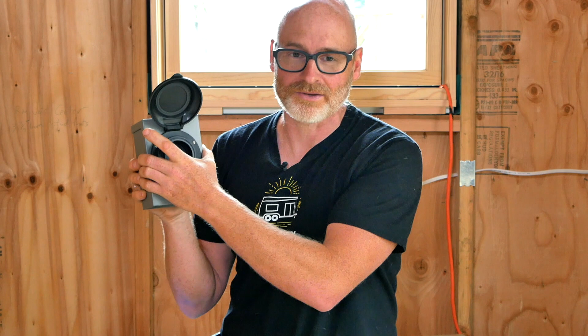It is a super dangerous thing to do, and this is a mistake that even electricians have made before, creating serious problems. So if you're going to use an RV box like this with a 240 volt plug, and use one of those adapters to bring it down to 120 volt, if you're somewhere with only 120 volt, you cannot have any 240 volt loads in your sub panel. You have to either cap off those loads, disconnect them, or rewire them to run on 120 volts. That's a super important thing to know about this.